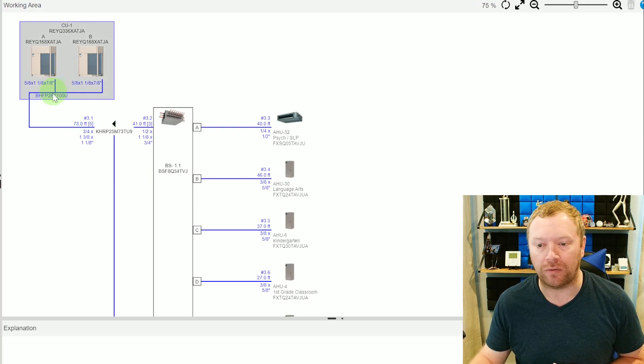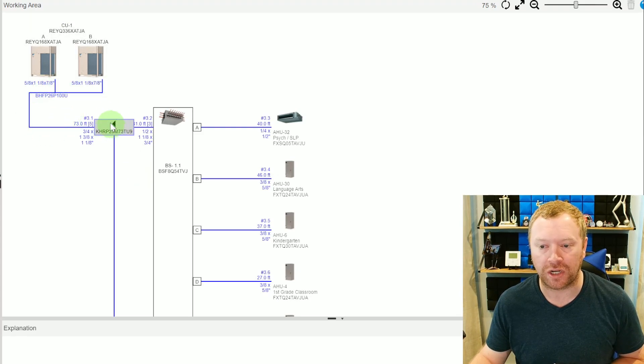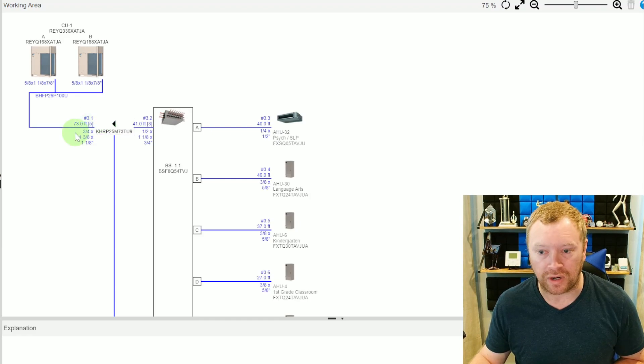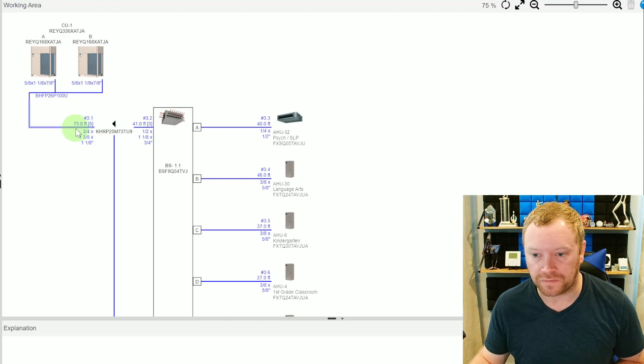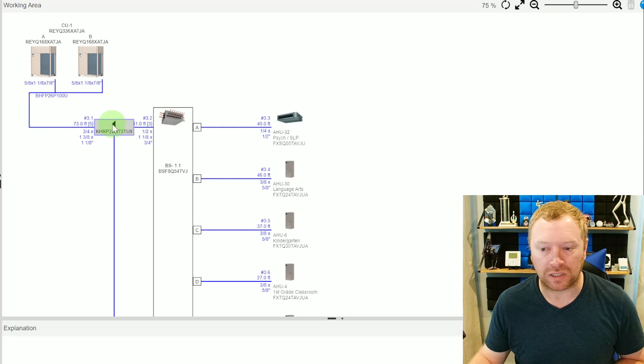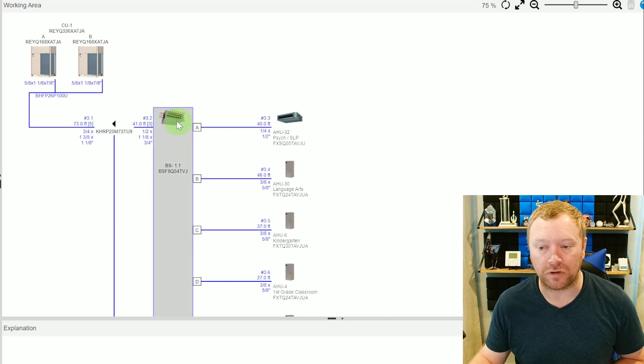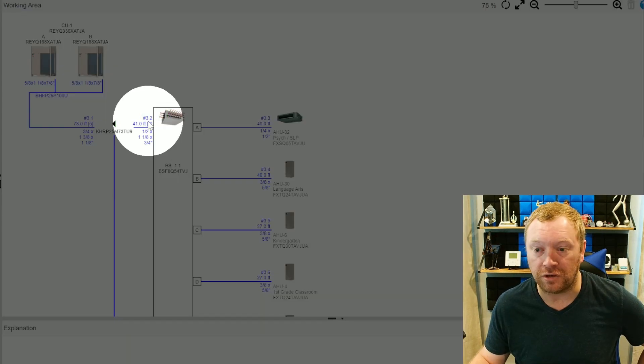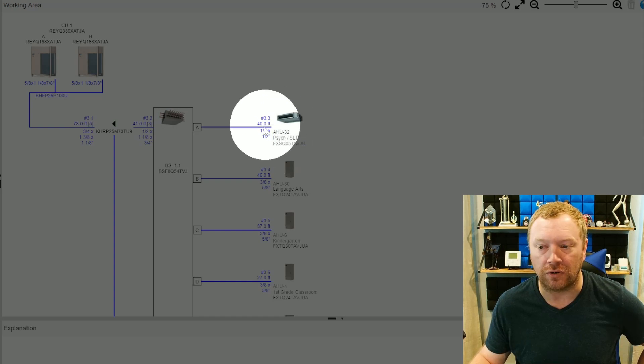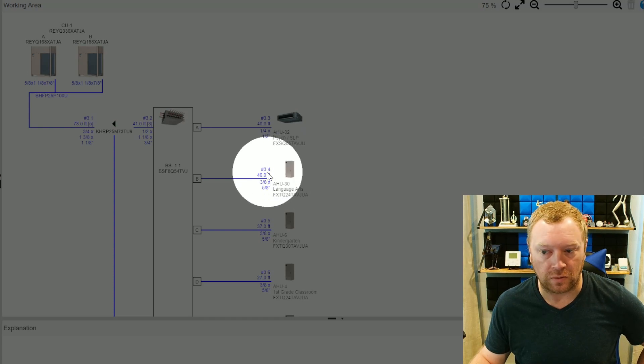But when you guys are installing VRF, you're going to notice that you have indoor units connected to a branch box. Maybe you have multiple branch boxes. So we split off our refrigerant lines. We go down to another branch box. You can see more indoor units on another branch box here. Based on the capacity of the indoor units connected to a branch box, and based on the length of all the line sets going back to the branch and to the outdoor unit, all of these are going to determine what the pipe size needs to be from point to point. We call these segments. You'll notice that from the outdoor unit to the first branch, this is segment labeled 3.1, and the length is 73 feet.